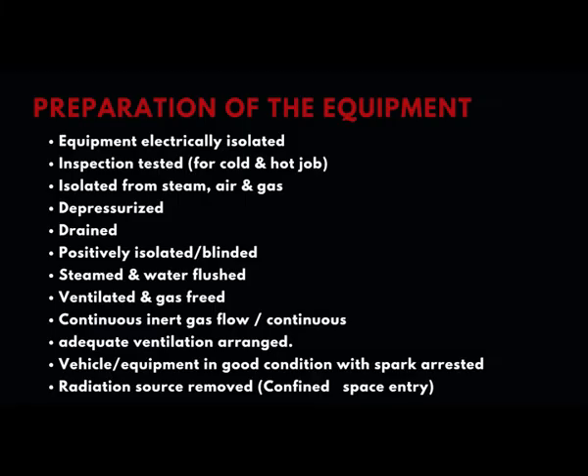Generally, people tend to think that by closing the valves, we try to isolate the flow of the stream inside the vessel, but in reality that need not be true. It is not enough to close the valve; you have to insert a metallic disc between the flanges, known as a blind.